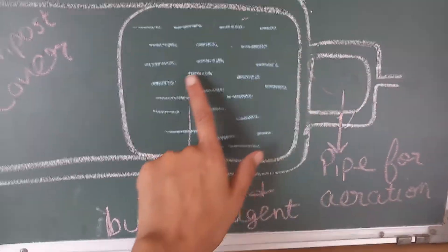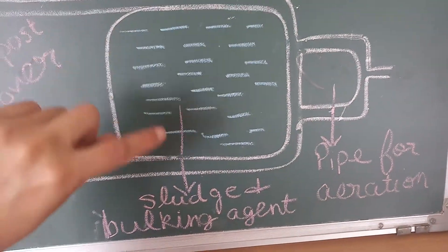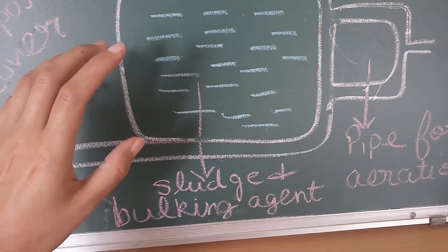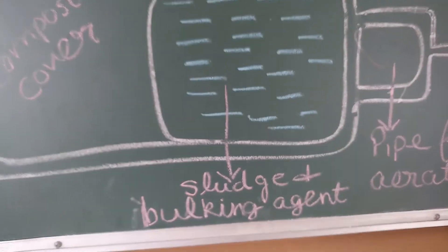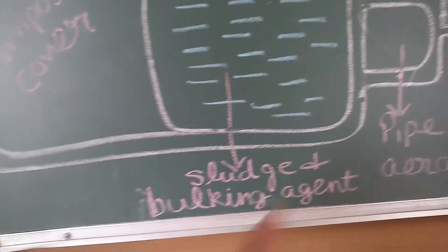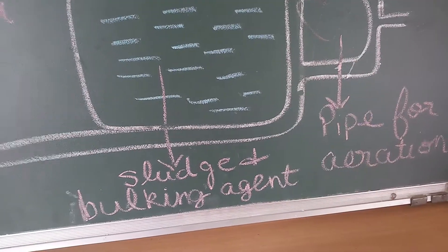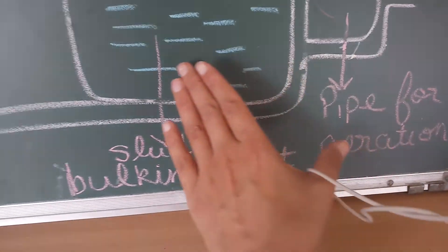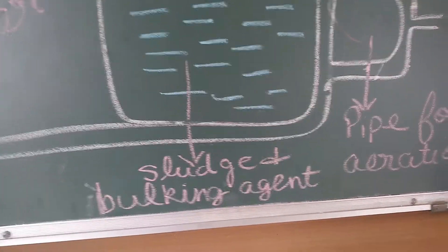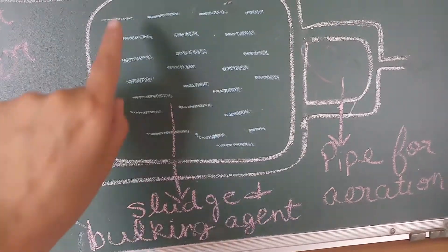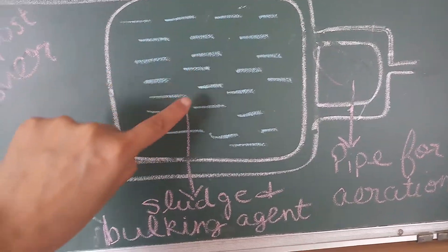This entire system is placed on a mesh or grid, with pipes running beneath it. The sludge and bulking agent — the bulking agent means wood chips — are placed over this grid of aeration pipes. Air is supplied through the blower for efficient aeration.